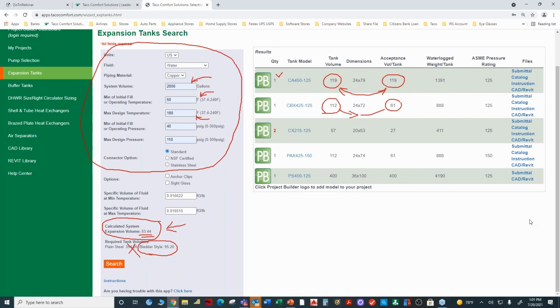Personally, I would err on the side of safety, if you know what I mean. Yeah, I would oversize expansion tanks. They're a static device. They don't have any electric motors, belts, fans, or rotating parts.